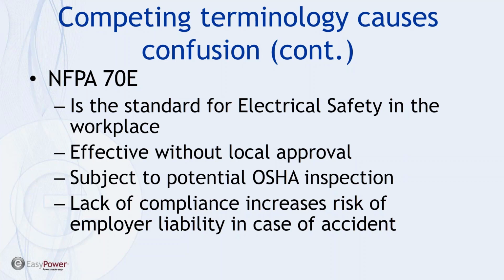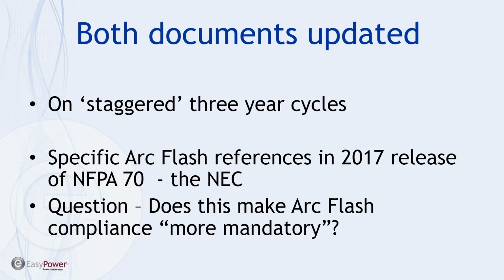Now, this confusion is not an issue on new construction, since most often the scope of work for new construction or additional construction on existing systems will include the verbiage requiring compliance with NFPA 70E. In that case, it'll be up to the project manager to ensure his checklist includes arc flash as part of that discussion. The real gap is whether a study is required on existing systems. So that's where I'm going with this.